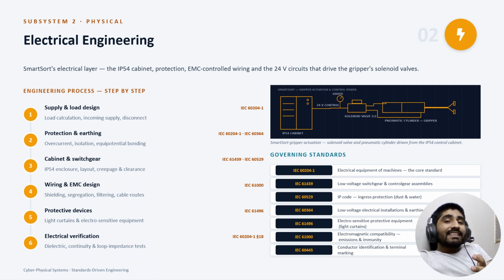IEC 60204 makes us calculate SmartSort's full load current, select the incoming supply, and fit a lockable main disconnect, so a maintenance engineer can isolate the cell and padlock it dead before reaching inside the cabinet.